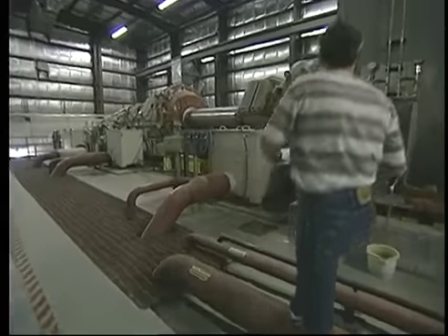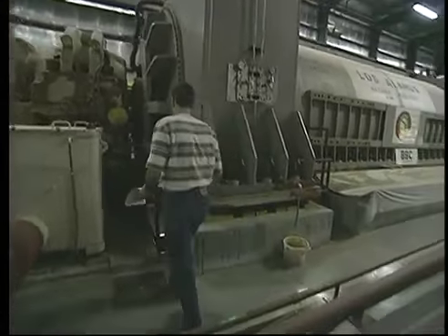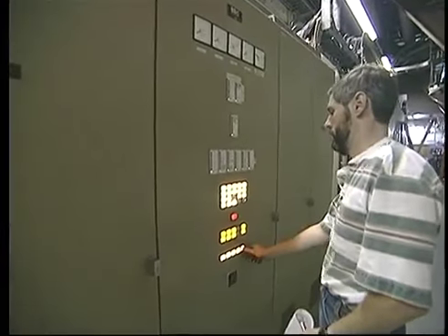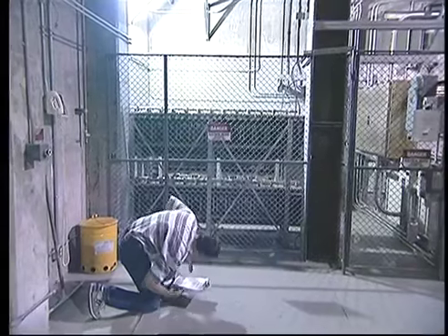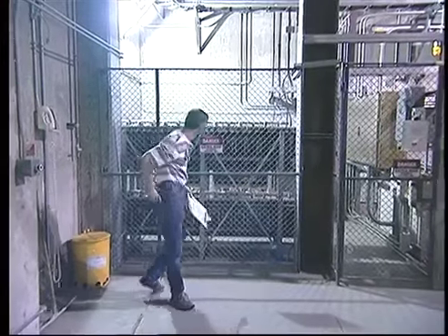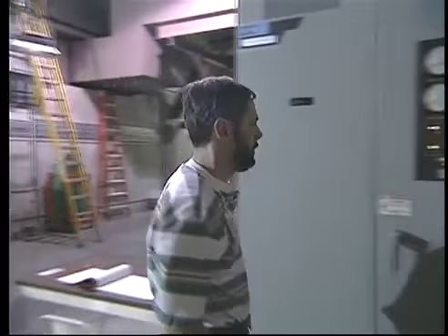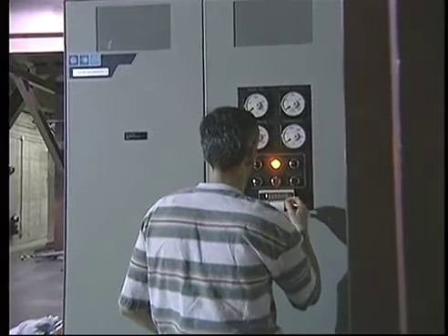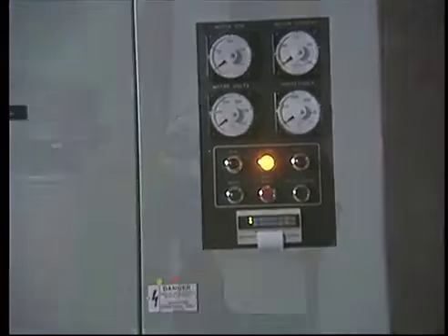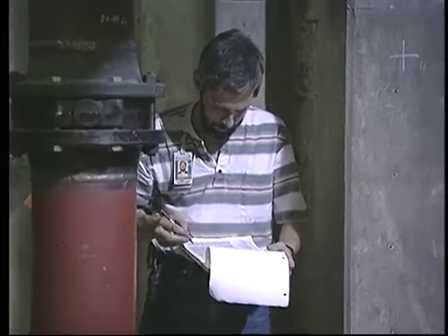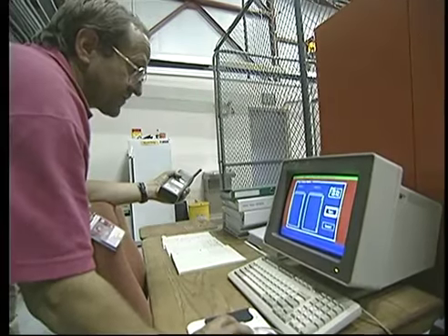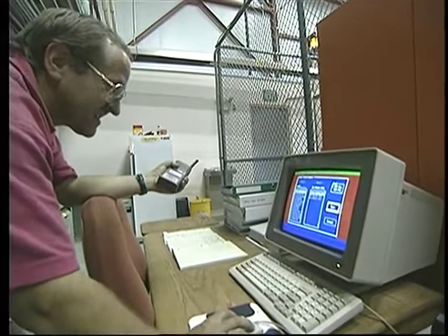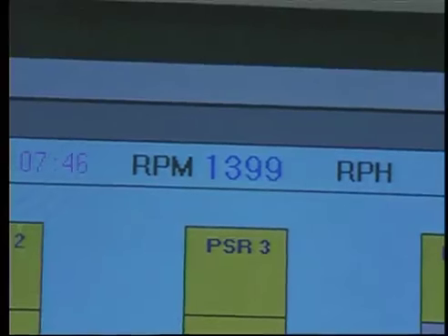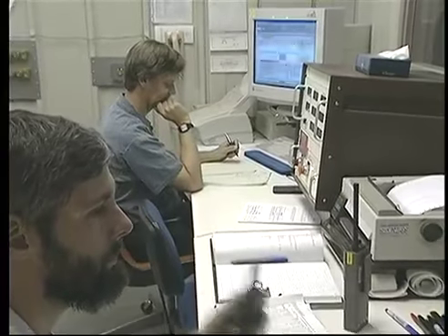While the experimentalists are busy at the magnet, the power generation team prepares the power source. Motor generator walkarounds ensure the status of bearing oil levels in circulation, cooling water levels in circulation, and lighting and power subsystems. Battery backup is available in case of commercial grid failure. Batteries would continue to supply power to critical control systems and pumps. Although the motor generator is a behemoth of a machine, it can be delicate when it comes to its operational needs.